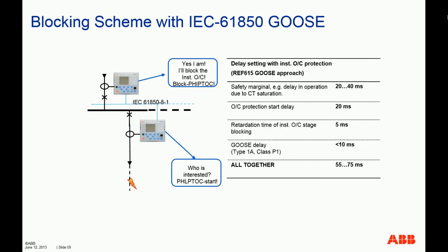Now, with modern substation automation communication technology in place, such as 61850 GOOSE, peer-to-peer event publishing, it has been estimated that the time delay mentioned here can be cut and reduced significantly. Altogether, it can save about 50 milliseconds of delay time based on the relay-to-relay communication. In addition to that, obviously, you would get rid of tons of inter-panel, inter-relay wiring, termination work, and labor. All of that can be saved through this type of peer-to-peer communication scheme.